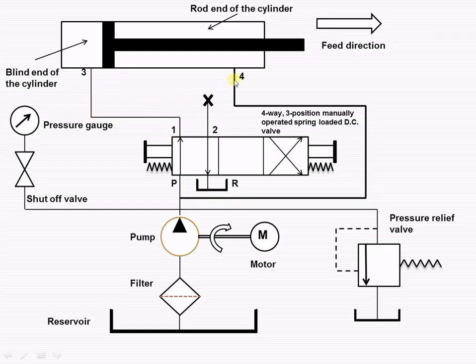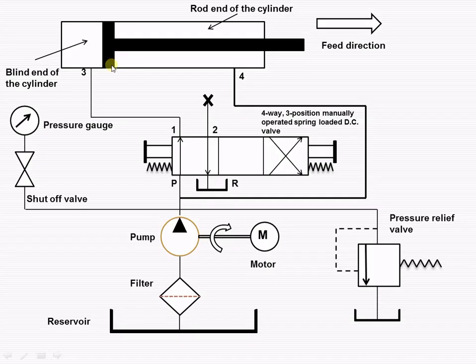Apart from the pump flow, the fluid from the rod end of the cylinder will also get added to the flow of the pump. The volume of fluid supplied to the blind end of the cylinder is therefore greater than the pump flow rate, and the speed of extension of the piston in the cylinder is greater than the retraction speed. This is known as regeneration — the regenerative circuit is used for increasing the speed of the piston in the forward direction.